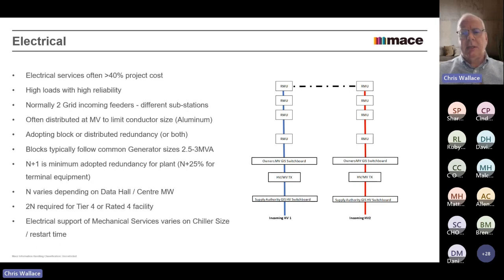So typically you set these things up, and each ring main unit feeds a block. And the block, again, I'll show you on the next slide, will normally be determined by a generator size, because you're going to say, in the event of my mains failing and my losing all the power from both sides of the ring, I'm going to need to feed that block from a generator, and therefore the generator size is going to determine typically what that block is. How many of the blocks you use will depend on what the load is in your data center.